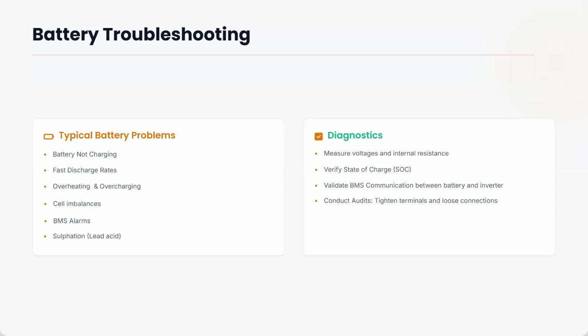The fast discharging rates mean that there's increased load or cable partial contacts or something, the battery cable or breaker will have a problem. Then it will look like it's discharging really, and it will tell you low battery in most cases. So meanwhile, your battery may not be low. But if the battery is fast discharging really, then something is wrong. Either it's not properly charged and then it's now discharging, or you have too much load on it. So that's that.